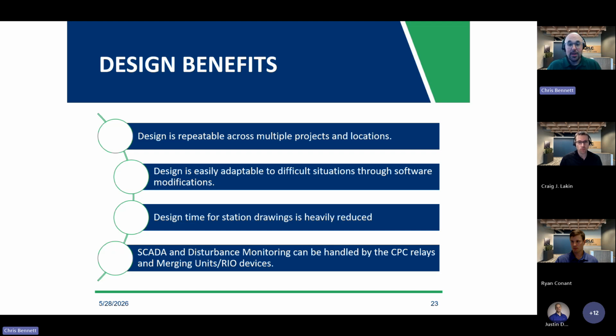So design benefits, on top of what we talked about before, the adaptability is probably the biggest factor here. We've all been in the situation where I wish I could copy and paste a certain breaker or relay set into my package, and I cannot because each breaker needs something else. It needs something different, something special. In this case, with merging units or even hardwire design, you can keep everything almost exactly the same between different station configurations and still get a massive benefit, and your design time is greatly reduced on paper.